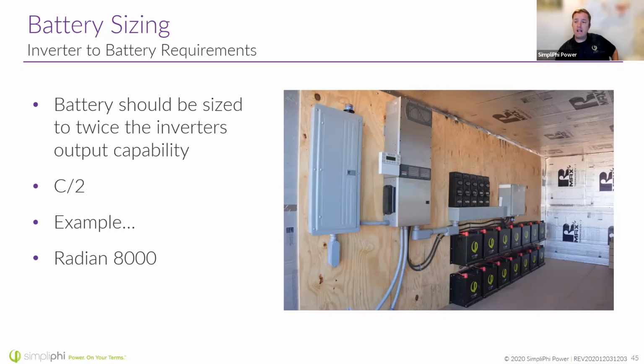So if you've got a Radian 8000, you want to see 16,000 watt hours of batteries, or 16 kilowatt hours of batteries, so that at no moment will that Radian ever try to pull more power out of those batteries than they're able to handle continuously.